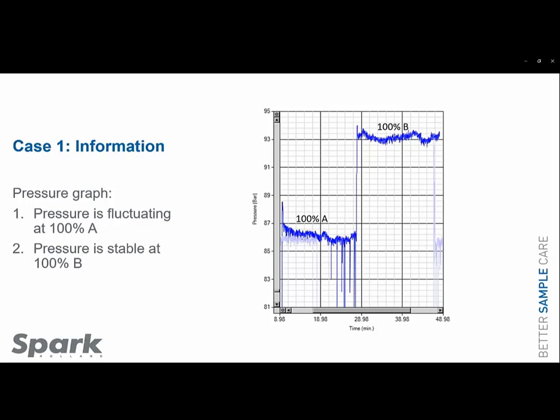We gather information. We start running the pump for 100% A. We observe pressure fluctuations on 100% A, as you can see in the pressure graph, which is available in the maintenance screen. You can see the pressure dips in here. If we run 100% B, there are no pressure dips. It's a complete flatliner. So we suspect pump A to be the source of the issue.